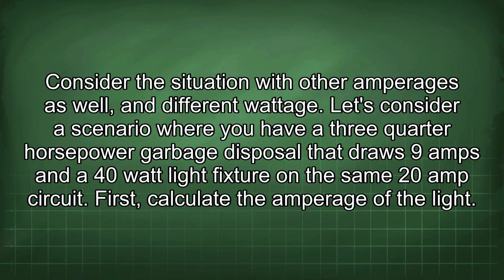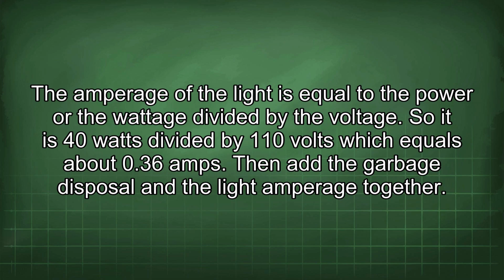Consider the situation with other amperages as well and different wattage. Let's consider a scenario where you have a 3/4 horsepower garbage disposal that draws 9 amps and a 40-watt light fixture on the same 20 amp circuit. First, calculate the amperage of the light. The amperage of the light is equal to the power, or the wattage, divided by the voltage. So it is 40 watts divided by 110 volts, which equals about 0.36 amps.